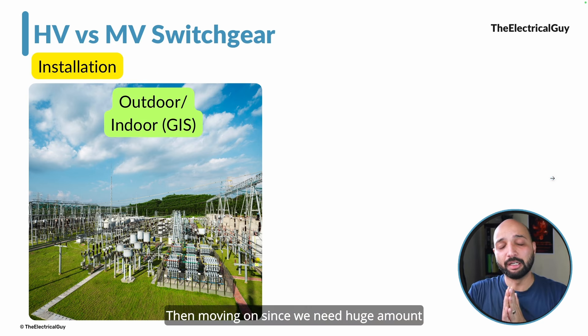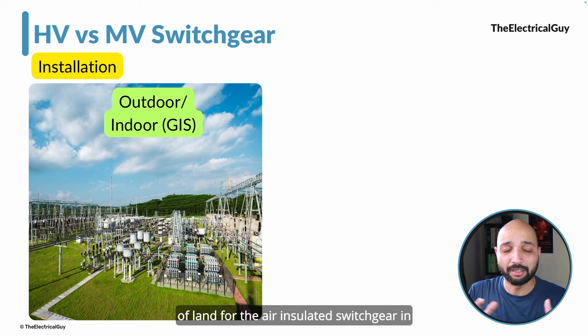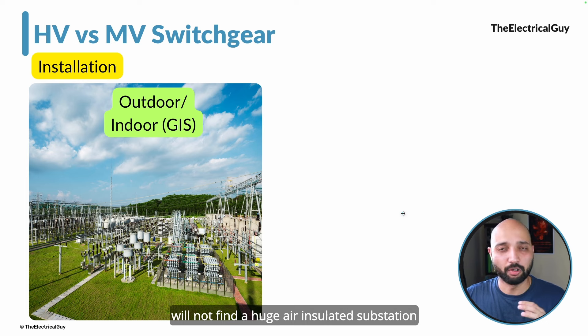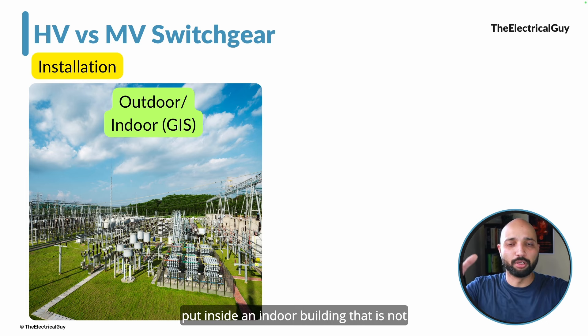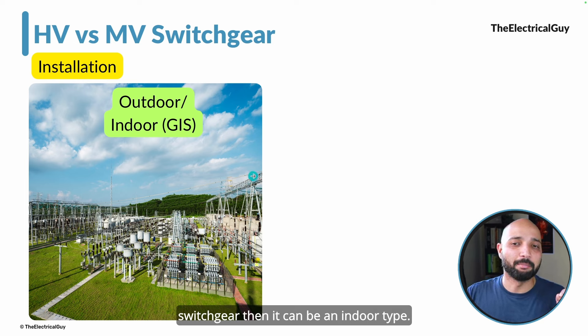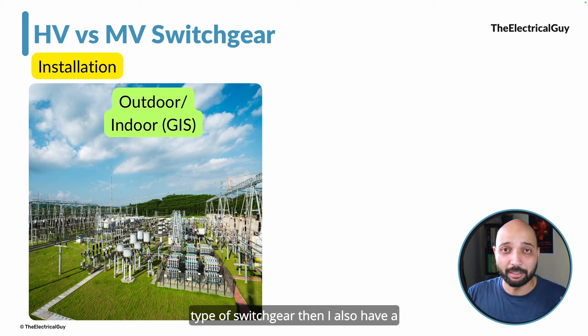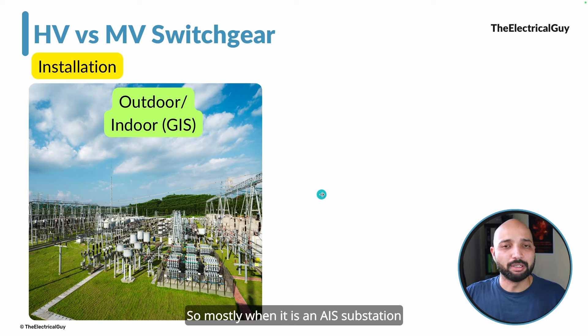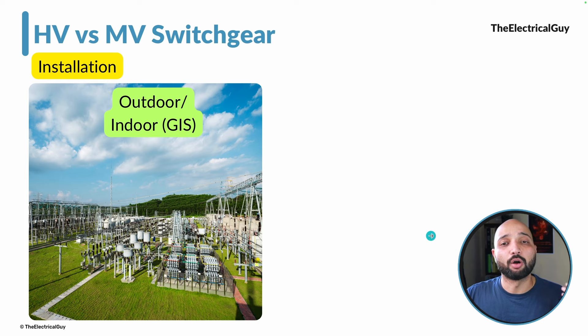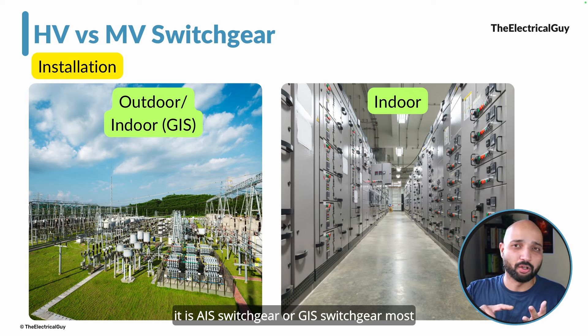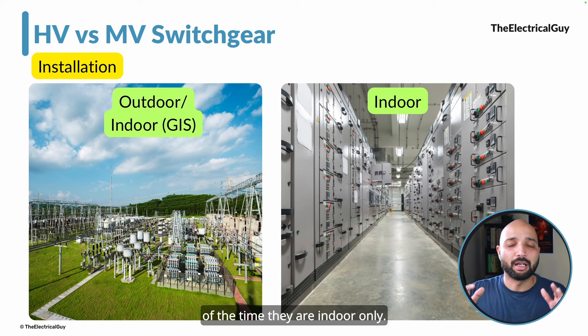Since we need a huge amount of land for air insulated high voltage switchgear, these substations are mostly outdoor. You will not find a huge air insulated substation inside an indoor building. If it is a GIS type, it can be indoor. But mostly when it is an AIS substation it is installed outdoor. In medium voltage, whether it is AIS or GIS switchgear, most of the time they are indoor.